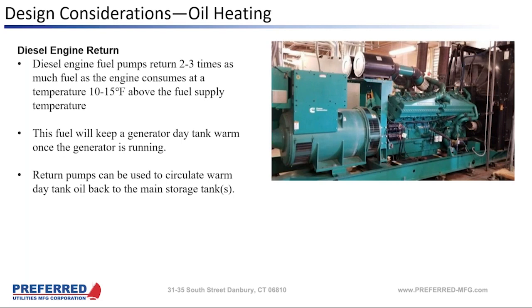So I had a plant in 2021 that was having a big emergency. They'd lost power. They could only get one of their gensets to come on, but that genset was running great, and they were having issues with their fuel system. They noticed that on the day tank where the engine was running, they didn't have any snow on that day tank. That tank had gotten warm enough to melt all the snow off of it.